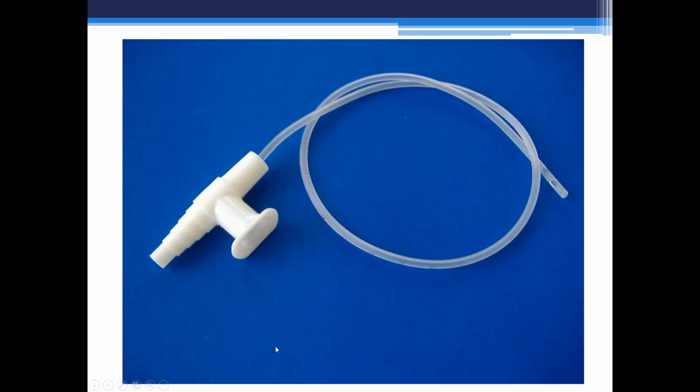Here's an example of that French suction catheter. In order to utilize this, you're going to remove your Yankauer tip from the suction tubing, and then this port here is going to be slid into that suction tubing. This is going to be your tip where you actually insert it in that patient's nose or mouth. And then in order to create suction, you're going to take your finger and just cover up this port here, which is going to direct all of that pressure to come out of that suction tubing tip.